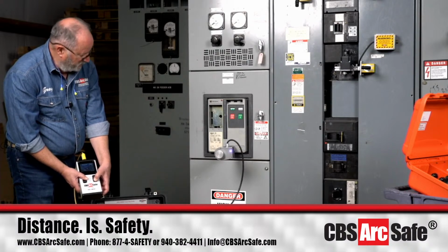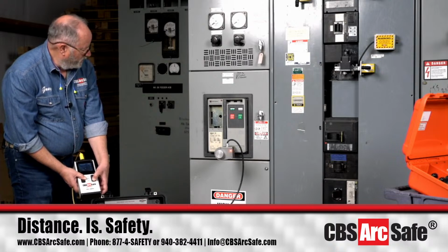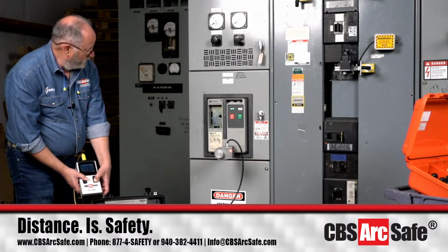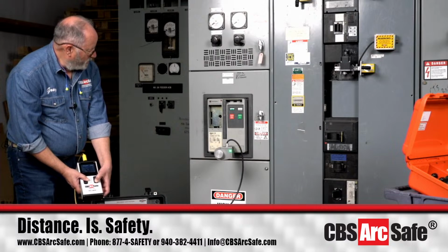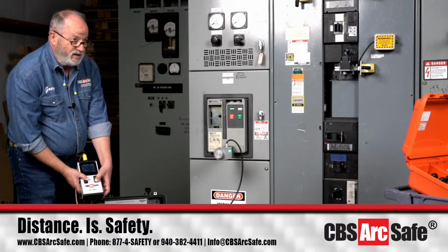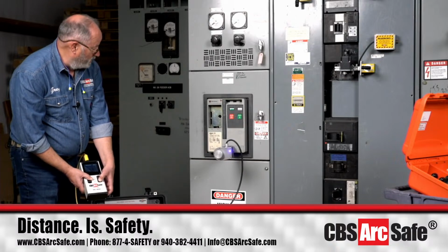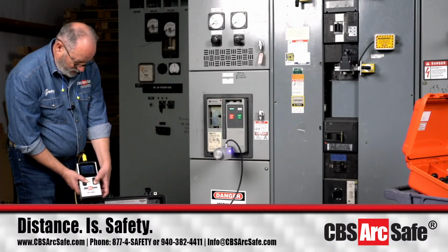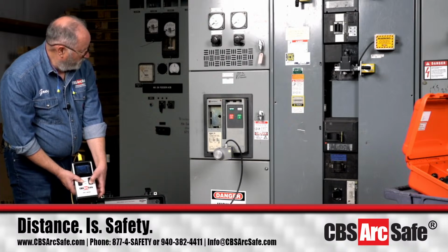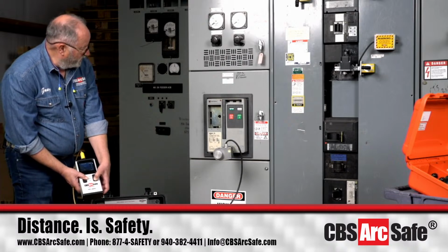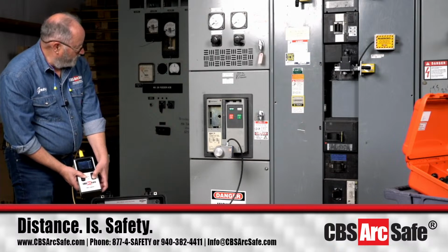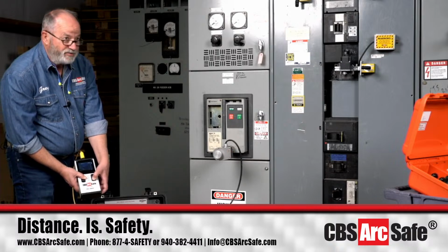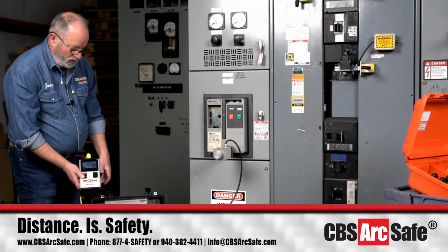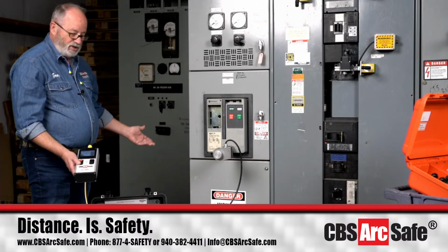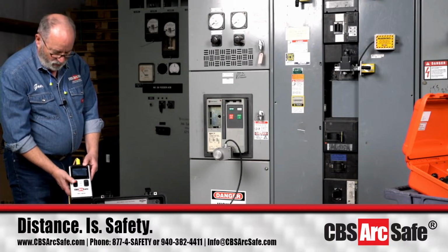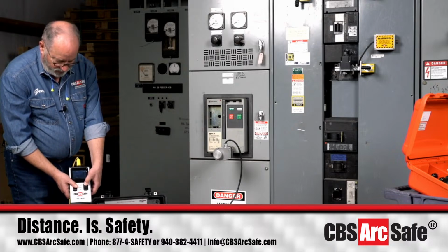It's right now showing in the test position, and we'll get to the disconnect in just a second. Remember, the test position simply has the secondaries connected, so if you want to run a test there, you can. You can see the indicator on the camera showing where you're at. It's going to go all the way to the end and release the torque, so I'll hold it down, and then it goes back just a little, about a half a turn. For us to move the breaker back in, it's the exact opposite process: we hold the enable button down, and now we go in.